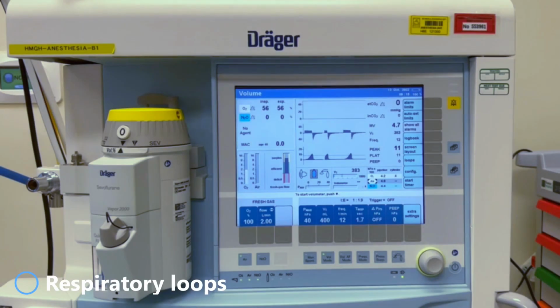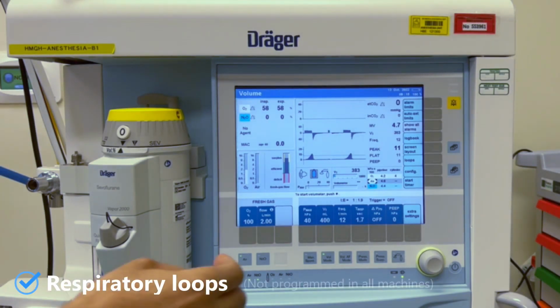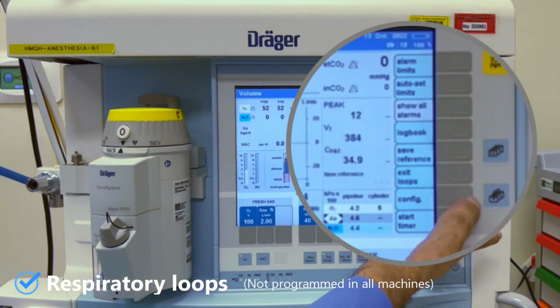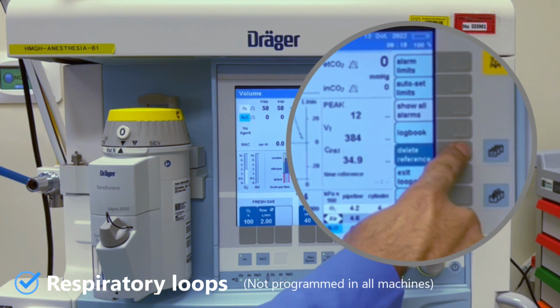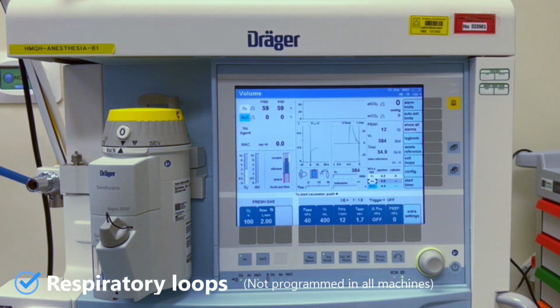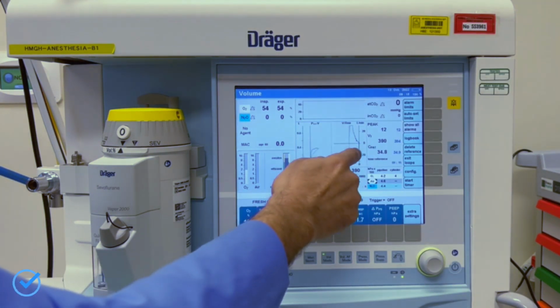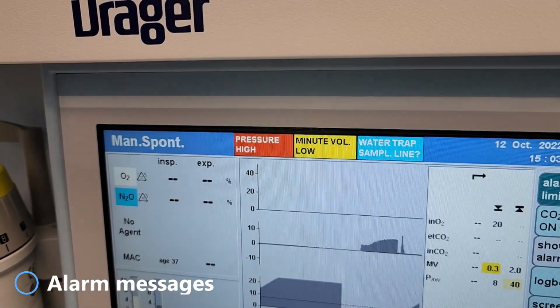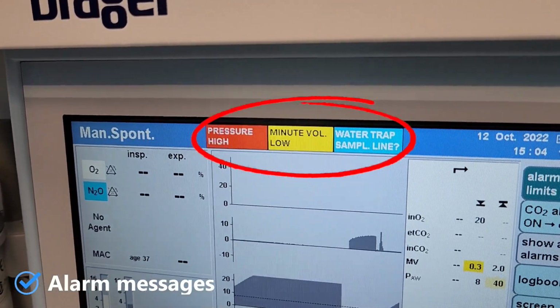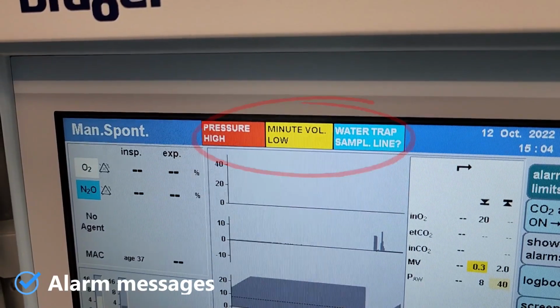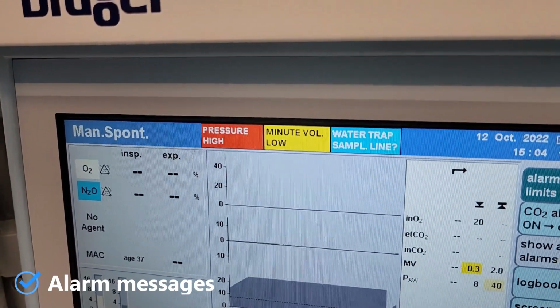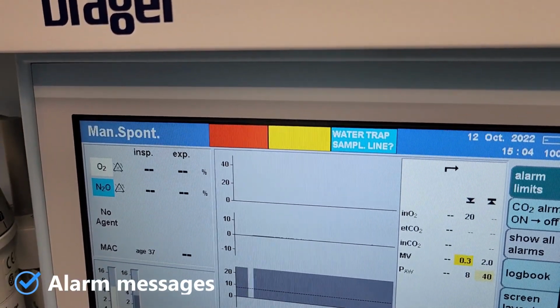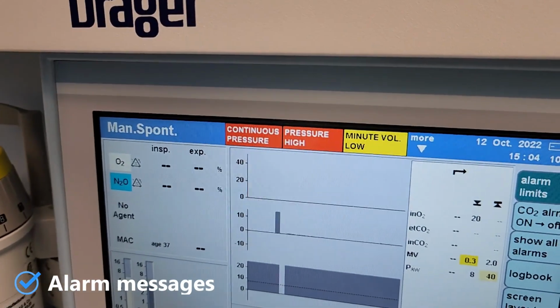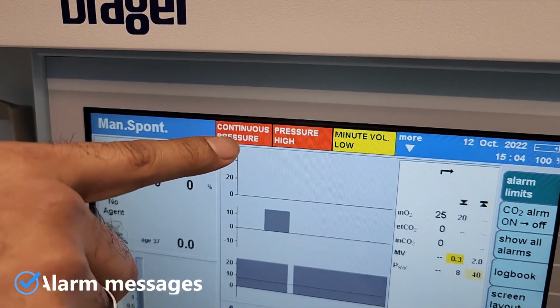To save the respiratory loops as a baseline to compare later, just press the loops button, then press Save Reference. The loop will be saved in blue color with time and values. Alarm messages are color-coded: red, yellow, and blue. Color is according to importance levels. Messages with the highest importance are in red color. This means it requires immediate attention.